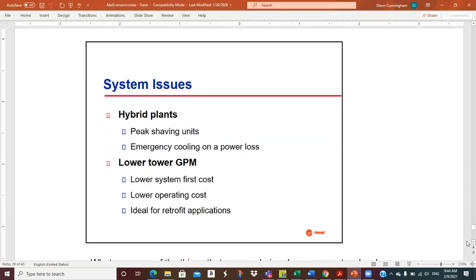When are we seeing absorbers? Well, these hybrid plants, and that had to do, in our economic example, with saving demand cost during a peak demand period of the day. And there are places in the country where that demand charge probably is between $24 and $28 a kW. Now, we're not that high in Tennessee right now, but if you go to the East and West Coast, power costs are much more expensive. And so this becomes much more attractive to them.